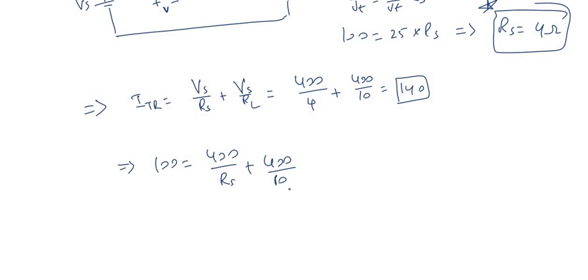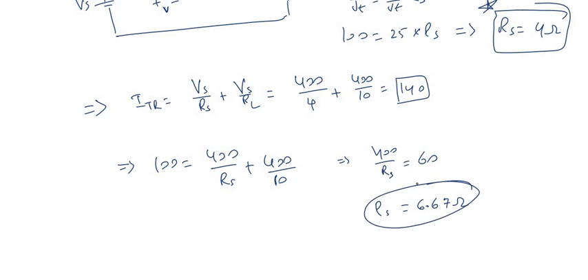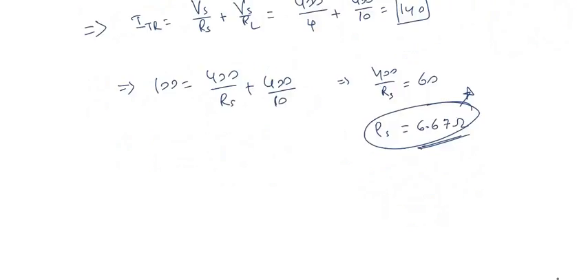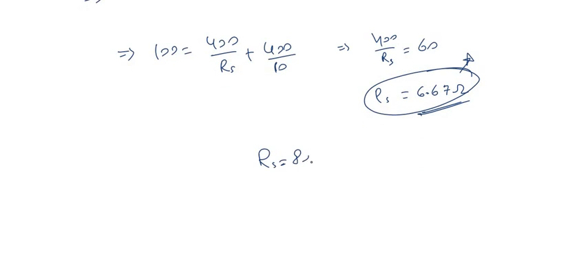What you will get: 100 minus 40 is the value, 400 by RS equals to 60. Now you will get the value of RS as 6.67 ohms. So whichever is higher between this, first we got 4 ohm and second we got 6.67 ohm, whichever is higher, that you have to select. So we generally select more than this. So for the safety purpose, let's consider the value of RS as 8 ohm.